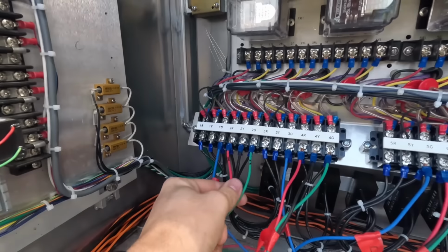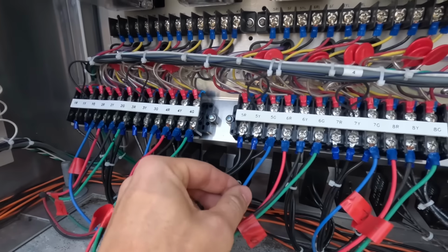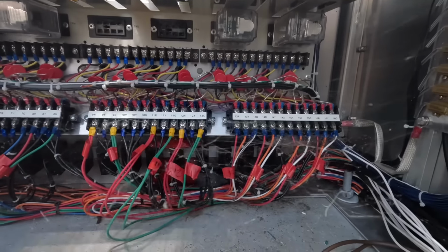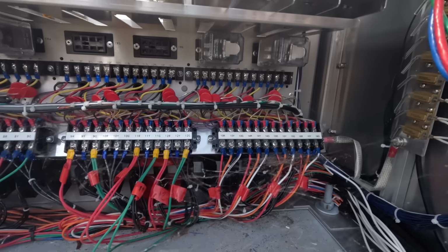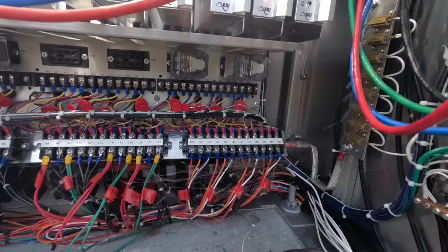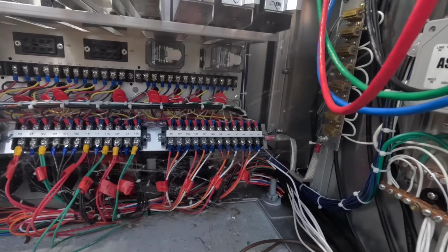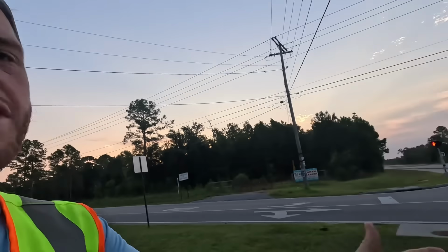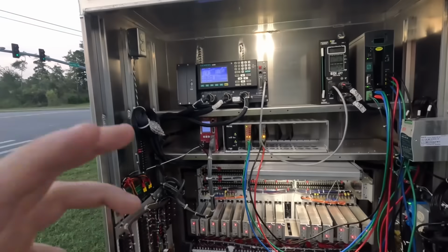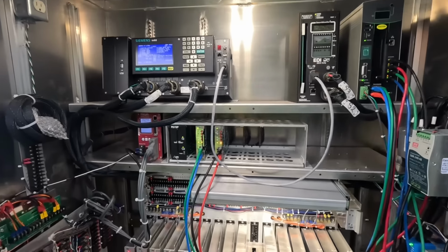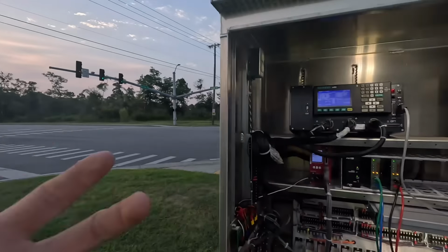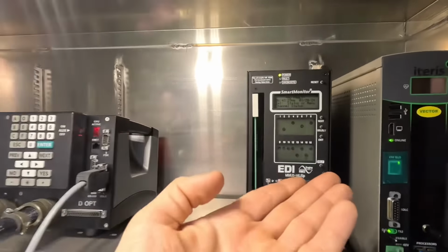So with phase 2, you also have phase 5, which is the green, and that's technically the phase. And then you have an overlap over here that's bundled up by a bunch of spider webs right now. But overlap C, which is landed on 15R, 15Y, and G, is going to be the red, the solid yellow, and the flashing yellow arrow, which is technically a green. So as far as the signal controller in this cabinet understands, that flashing yellow arrow out there is going to be picked up and monitored as a green light.